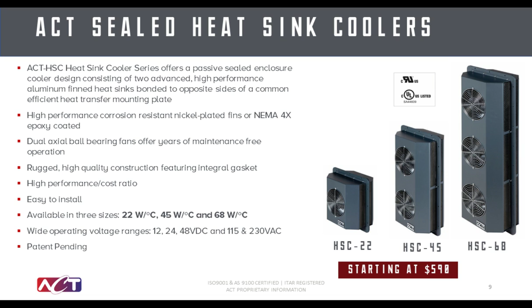The model number, if you are wondering, HSC22, HSC45, or HSC68, corresponds to a certain thermal conductance value. For example, if your application has a 20 degree C delta to work with and you are using an HSC22 to help cool that application, you would get approximately 440 watts of heat dissipation capability. This calculation similarly works with any delta with any of the model numbers to get not only the specific configuration you need, but also the number of units you may or may not need.